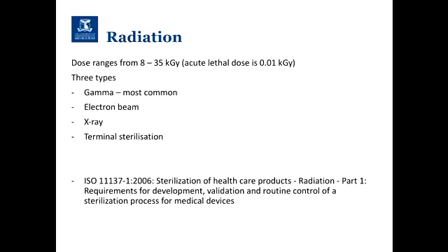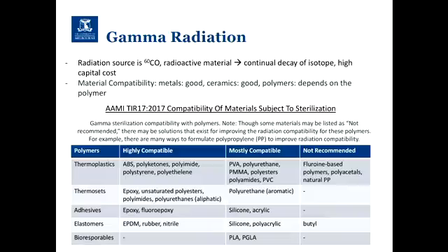I've put the standard for it. I had a read through it. If you'd read through the ISO 10993 standards and thought they were a little bit dry, then I wouldn't recommend reading this. But it's essentially telling you what sort of doses you need and what procedure you have to go through to sterilise a medical device using radiation, and to be able to validate that process as well. So that's one of the methods that's used for sterilisation.